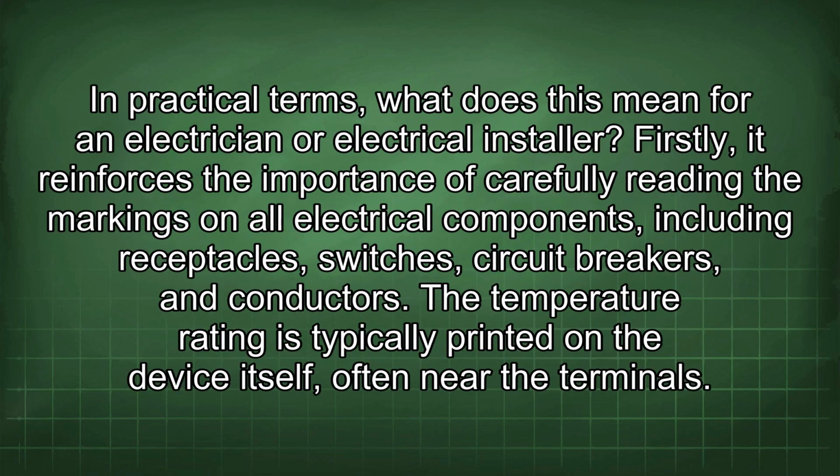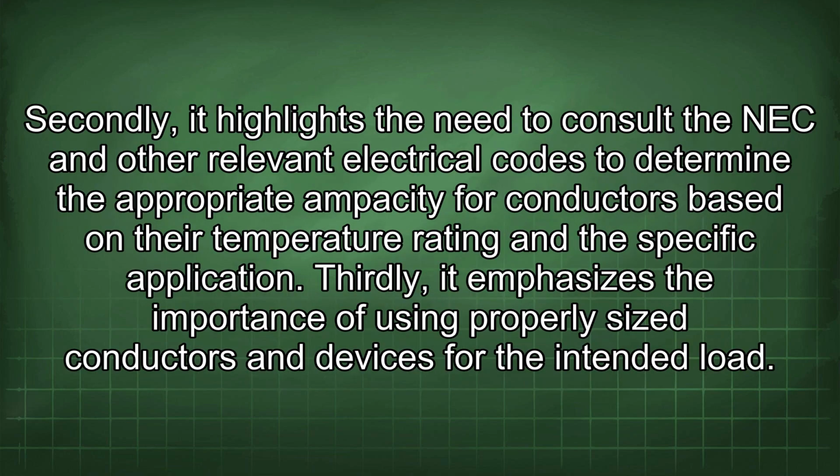In practical terms, what does this mean for an electrician or electrical installer? Firstly, it reinforces the importance of carefully reading the markings on all electrical components, including receptacles, switches, circuit breakers, and conductors. The temperature rating is typically printed on the device itself, often near the terminals. Secondly, it highlights the need to consult the NEC and other relevant electrical codes to determine the appropriate ampacity for conductors based on their temperature rating and the specific application.